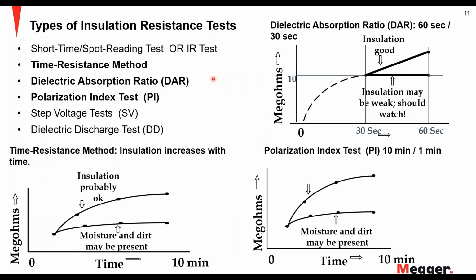So there are different types of insulation resistance tests that you can do on an equipment. There is a short time spot reading, that is basically you connect your equipment, measure, and boom, done. So you are doing a spot reading, that is you're essentially connecting the instrument and immediately taking a reading after your test voltage is reached. That's your spot reading.